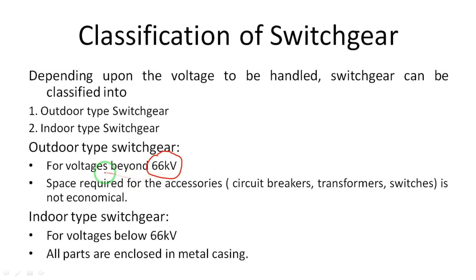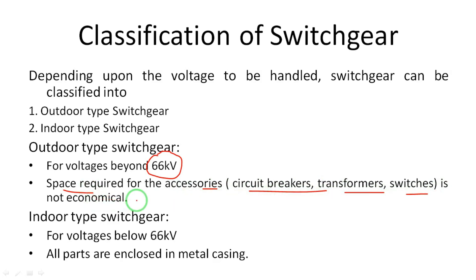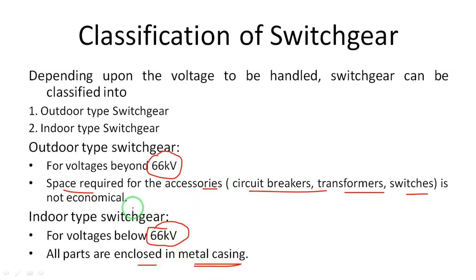Outdoor type switchgear is used for beyond 66 kV because it requires large accessories that also require large space, so it cannot be used in an indoor system. These accessories include circuit breakers, transformer switches — they are large and not economical for indoor use. For below 66 kV systems, the accessories are of enclosed type, enclosed in metal casing, so they can be used in indoor type switchgear systems.